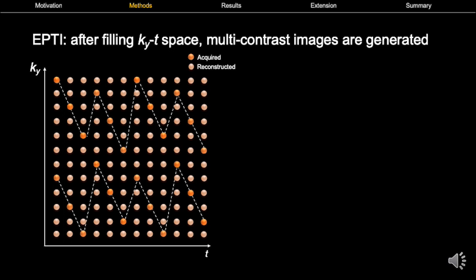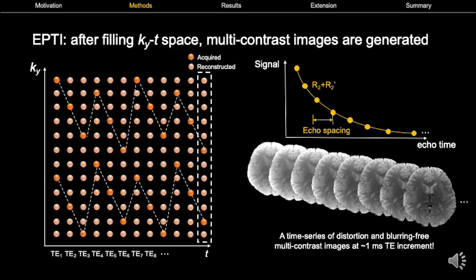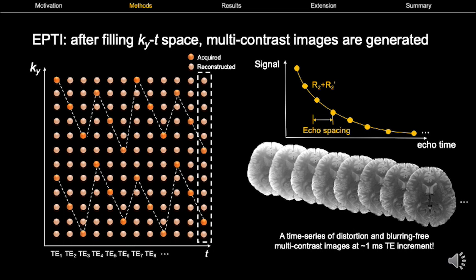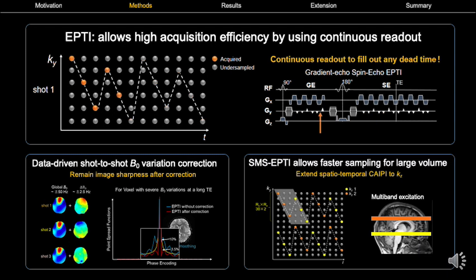This reconstruction nicely fills out the KYT space. By applying inverse Fourier transforms along phase and frequency encoding directions at each echo time, we can get more than a hundred distortion and blurring-free multi-contrast images at one millisecond TE increment. This sampling allows high acquisition efficiency by using continuous readout to fill out any dead time in the sequence. A data-driven shot-to-shot B0 variation correction was also developed to maintain image sharpness even with strong B0 inhomogeneity. We also extend EPTI to the slice direction by combining it with SMS for faster sampling of large volumes.